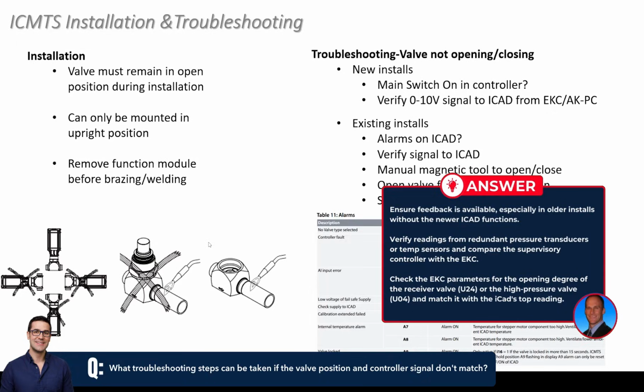That was a newer function that we added into the iCAD. So especially on older installs, that's probably not even there as an option. And when we do have it, it is just a feedback of that signal. There's no infrared technology or anything along those lines happening within the valve to actually confirm the opening degree.